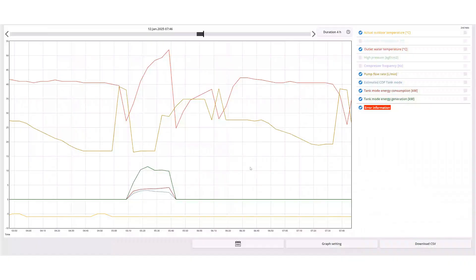As a conclusion, in my opinion, if you compare different cycles or different houses with R290 versus R32, I could not see a big difference. The main difference is design — so the volume, as we know, for the heat pump. But from refrigerant properties, R290 could be more efficient because we work at lower pressures, lower volumetric flows in the refrigerant part, and we have a higher latent heat of vaporization. This is similar to the comparison of glycol and water — with glycol, we need to spend more energy because we have a different heat capacity than water. The same principle can be applied to R32 and R290.